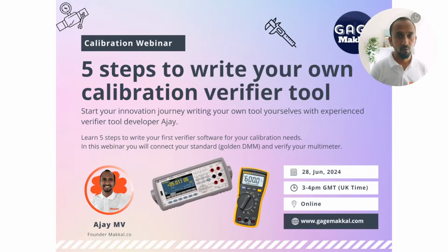So how do we go about writing our own verifier tool? In this webinar, we are going to look at using our own LabVIEW based tools to write a simple verifier that will test a multimeter and whether it is within the tolerance limits. It gives a pass or fail for the different tests that it carries out, and based on that we can do further tuning of the multimeter as we need. So let's get started.